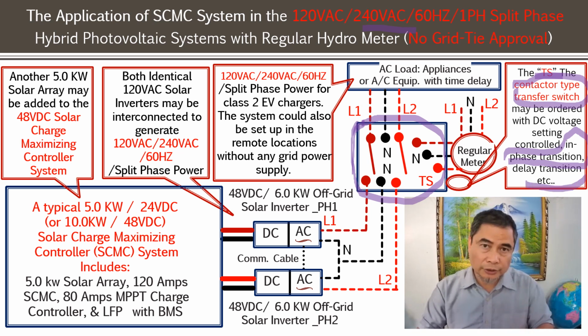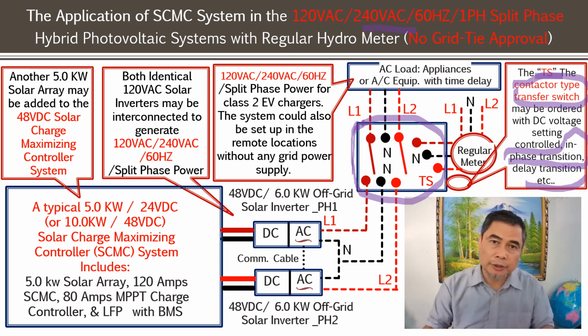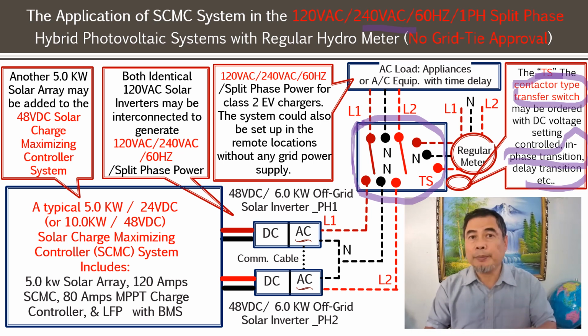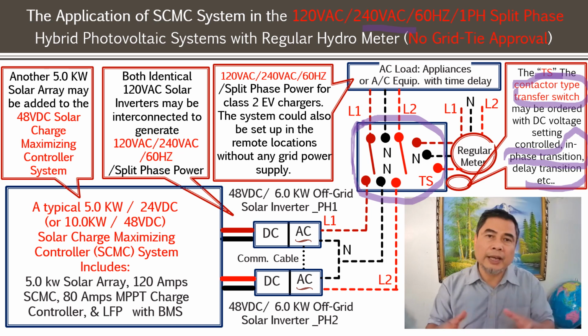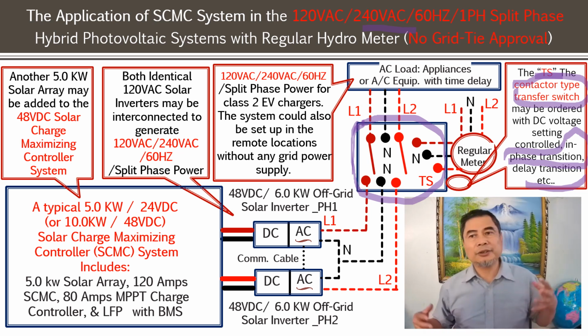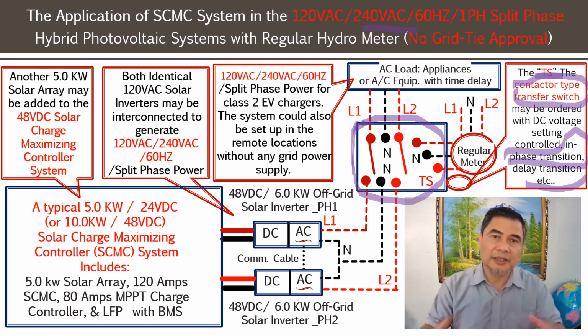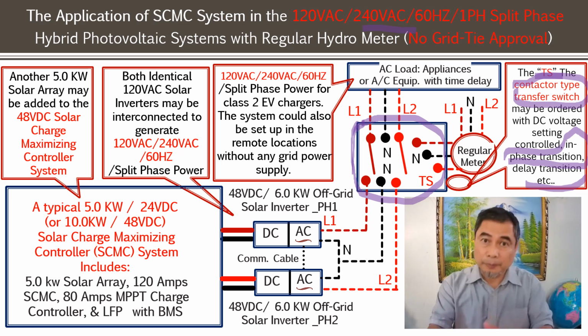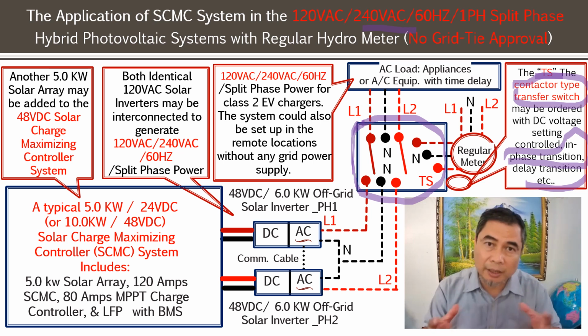the compressors will not take a sudden power outage and then power suddenly coming in, unless they have their own delay built in. As a matter of fact, some of the refrigerators and AC equipment already have that delay built in, in case the power goes out and then suddenly comes back, to protect the compressor, because when the AC equipment runs, the condenser of the AC equipment builds up high pressure.